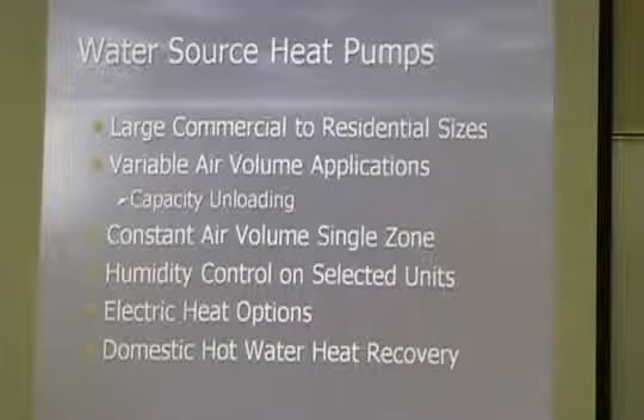Heat pumps start out at probably half a ton to 3/4 ton. The package units are the horizontal and vertical units. I think the vertical units probably go up to like 7.5 to 10 tons, and the horizontal units might go on up to 20 tons. Most manufacturers, you can even get a variable volume application in their heat pumps, meaning that you can add a drive to the fan.